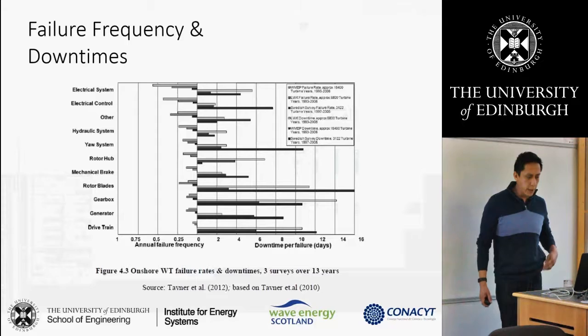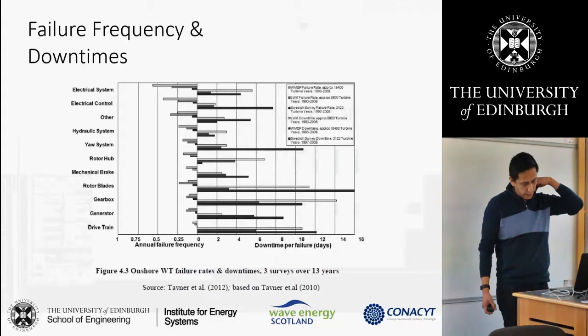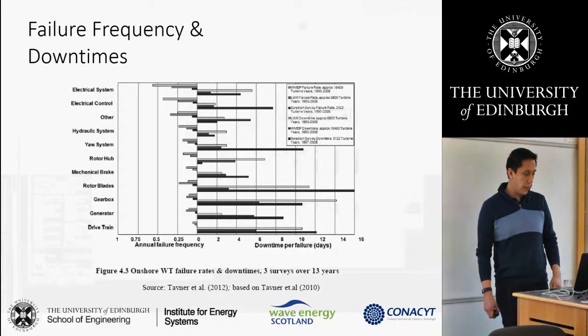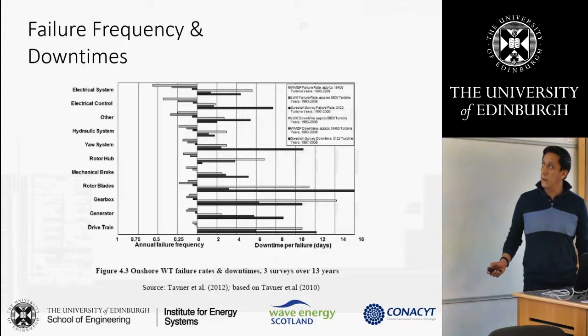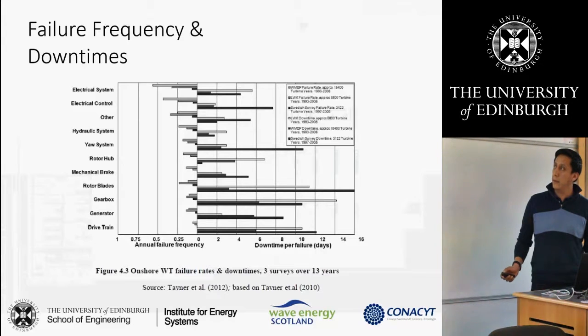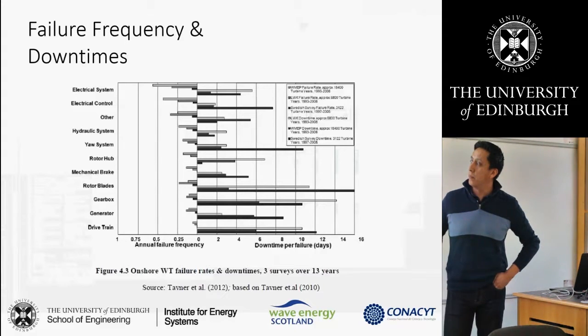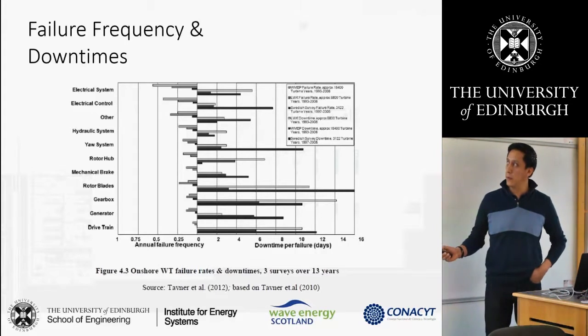Here is a graph of onshore wind turbine failure rates and downtimes from a survey gathering information over 13 years. We can see the importance of not focusing solely on failure frequency — for example, the generator and gearbox have a low annual failure frequency, but the downtime per failure is very large. So it's very important to focus on reliability.